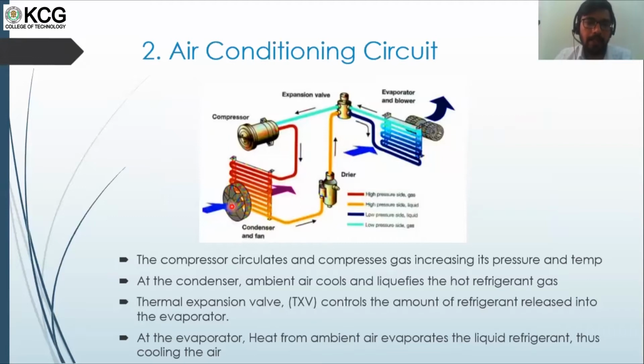The condenser fan blows cold air over the condenser so that, while it is still at high pressure, it liquefies the gas. Now we have high pressure, liquid state refrigerant. The dryer ensures that only liquid refrigerant passes to the expansion valve. What the expansion valve does is regulate the flow of refrigerant as per the cooling requirement.